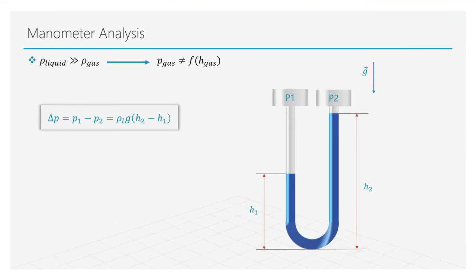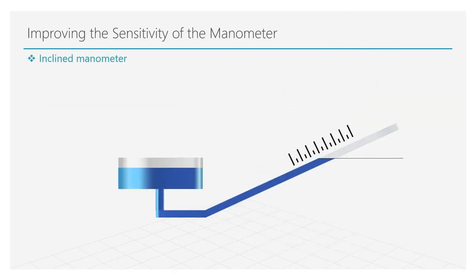There are multiple ways to improve the sensitivity of a manometer. One approach is to use an inclined manometer. In this configuration, the fluid covers a longer distance along the tube for the same vertical height change, allowing smaller variations of pressure to be visualized.